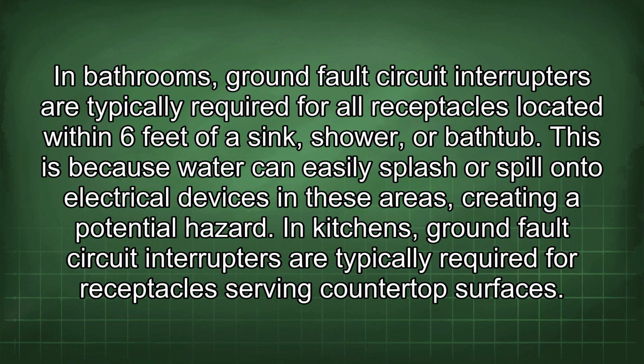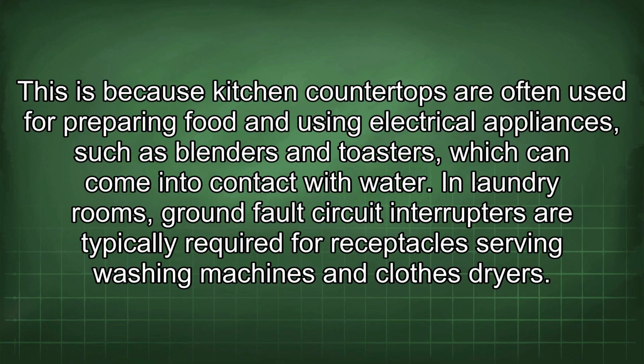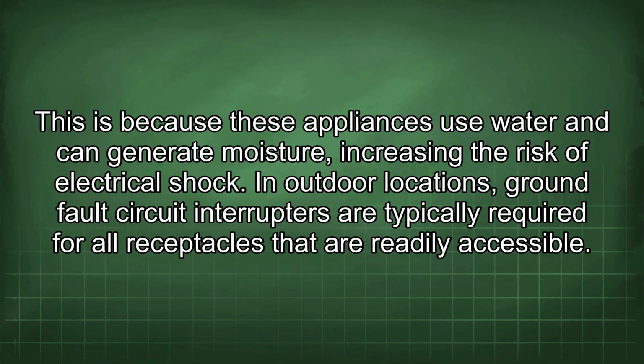In bathrooms, ground fault circuit interrupters are typically required for all receptacles located within 6 feet of a sink, shower, or bathtub. This is because water can easily splash or spill onto electrical devices in these areas, creating a potential hazard. In kitchens, ground fault circuit interrupters are typically required for receptacles serving countertop surfaces. This is because kitchen countertops are often used for preparing food and using electrical appliances, such as blenders and toasters, which can come into contact with water. In laundry rooms, ground fault circuit interrupters are typically required for receptacles serving washing machines and clothes dryers. This is because these appliances use water and can generate moisture, increasing the risk of electrical shock.